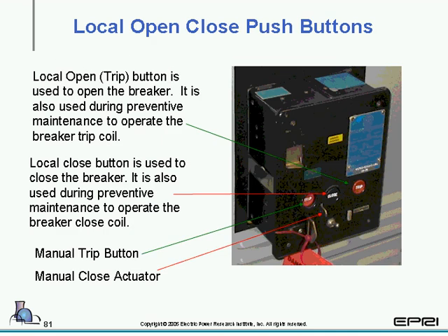And then on some particular designs, you may come across local open and close push buttons, which allow you to open and close the breaker electrically from a local point on the breaker. And then you also may come across some sort of manual trip button, which is standard on all breakers, and you may come across a manual close actuator, which does not actuate the closing coil, but uses mechanical leverage to actually trip the close latch to close the breaker.